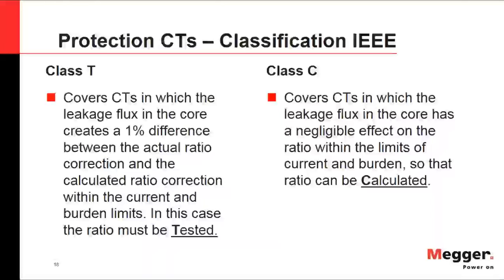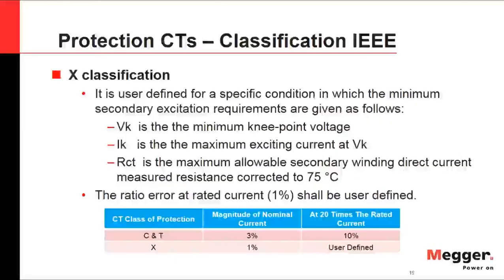There is also classification X, which involves agreement between manufacturer and end user. It requires defining the minimum knee-point voltage, maximum exciting current at the knee-point voltage, and the secondary winding resistance measured and corrected to 75°C. Standard burdens for protection CTs according to IEEE are 1 ohm, 2 ohms, 4 ohms, and 8 ohms.